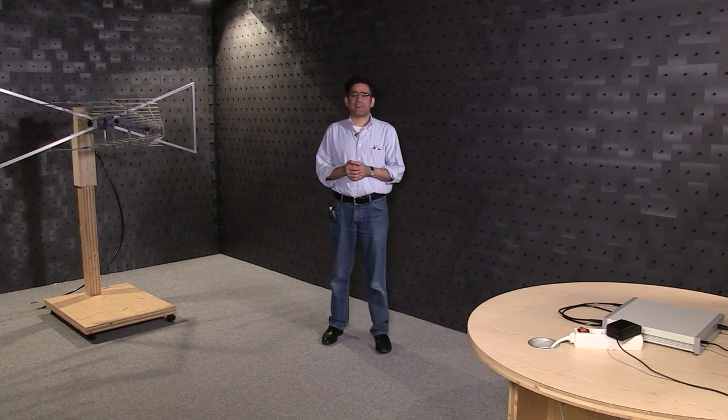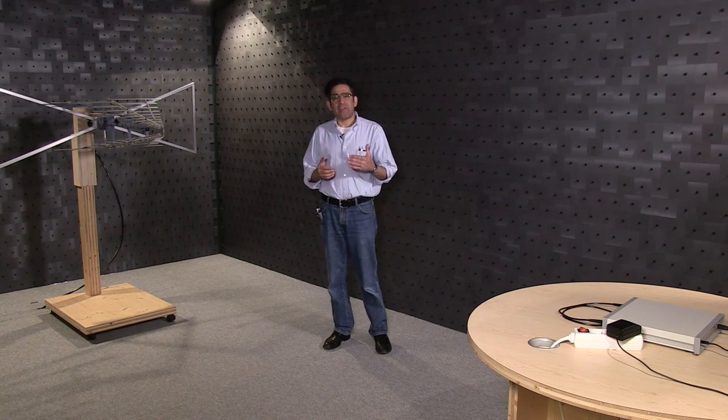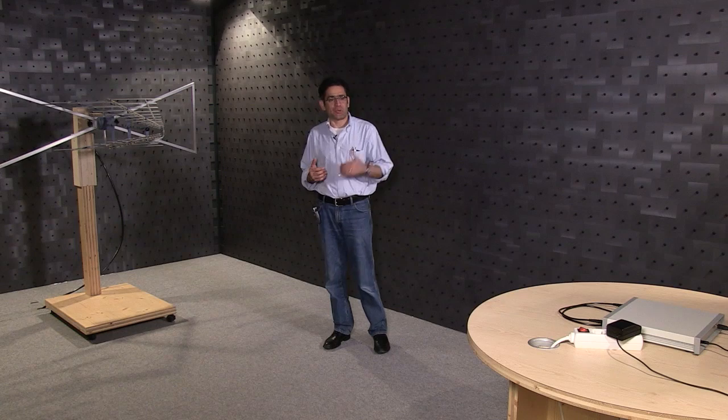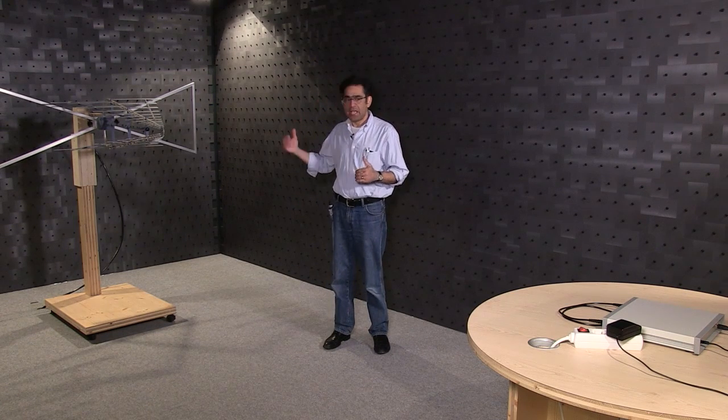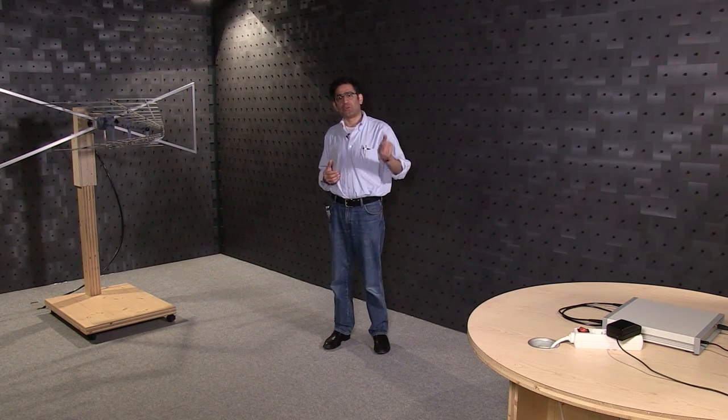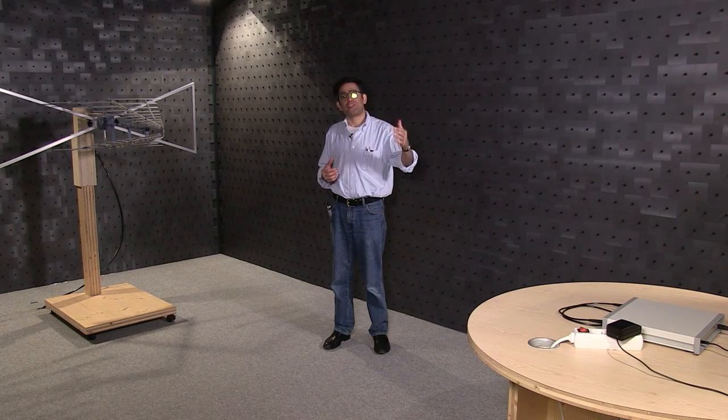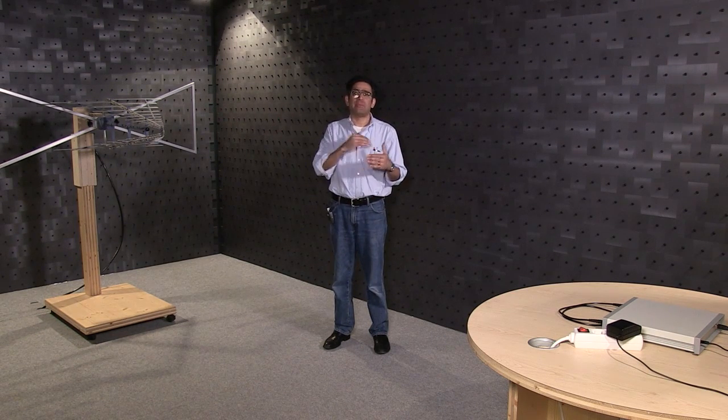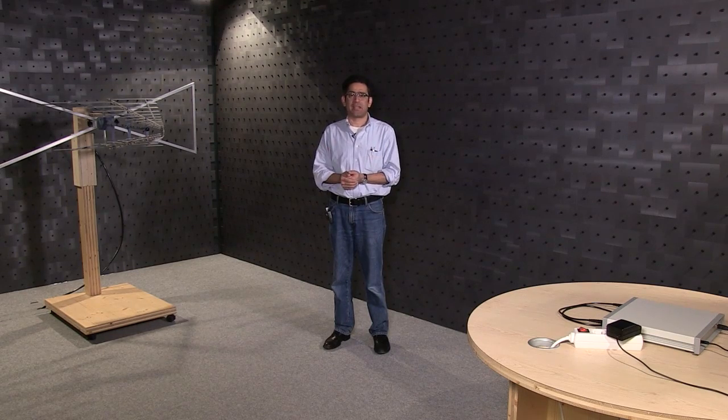The test setup is defined in the standard and it may vary slightly depending on your product or application but typically it is a wooden table and an antenna and the device under test is placed on the wooden table and the emissions from this are picked up by the antenna and then it is compared against a limit line which is again defined in the standard.